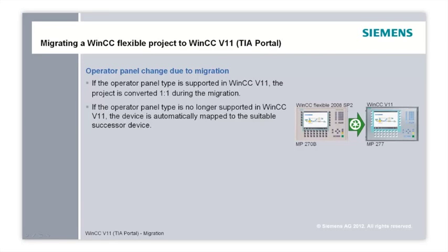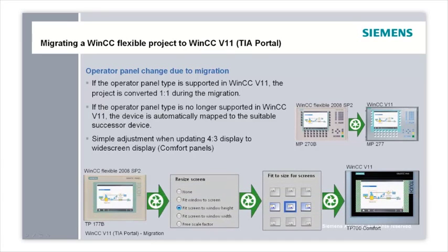You can specify prior to the migration how to place the contents of the migrated pictures on the new operator panel. This is a particular advantage in the case of widescreen resolution on the new operator panel. In the displayed example, the TP177B with a 4:3 resolution is migrated to a TP700 Comfort Panel with a widescreen resolution. In this example, the configured picture of the TP177B is adopted in the TP700 Comfort by the preset 'Fit screen to window height' option.